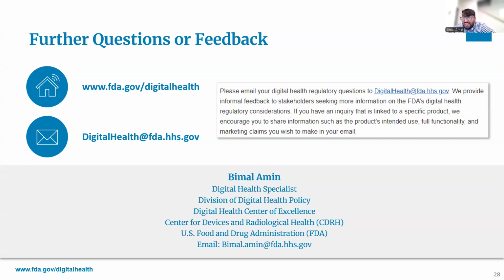digitalhealth@fda.hhs.gov. As I mentioned before, the FDA offers sponsors the option of a pre-submission, which is a valuable tool that fosters communication, collaboration, and regulatory alignment between sponsors and the FDA. It's voluntary and does not have any user fees.